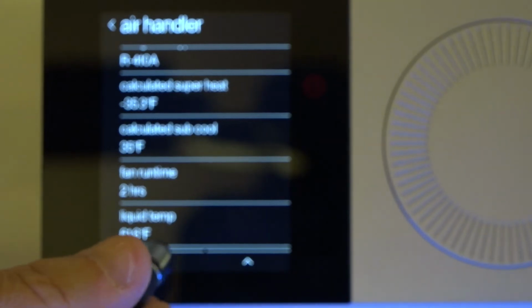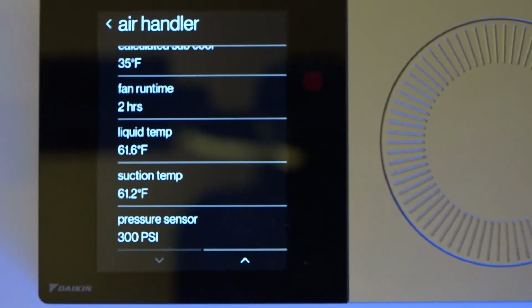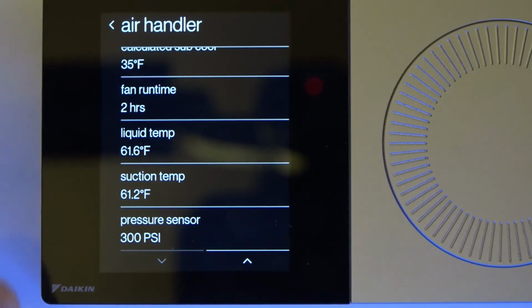I can get down here and see the thermistors and things that are inside the air handler, because we've got a couple thermistors and a pressure transducer and an EEV valve built inside the indoor air handler. So I get to see all of that information as well. So let's back out of this screen here.